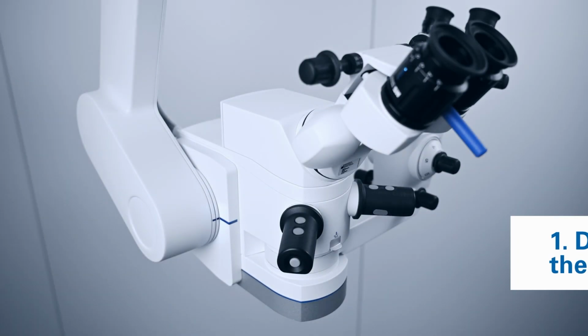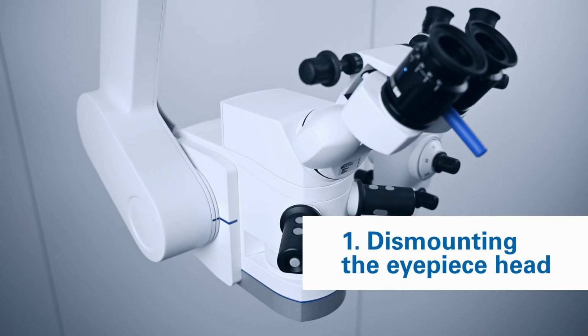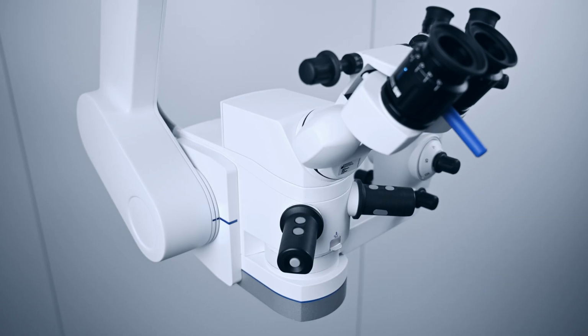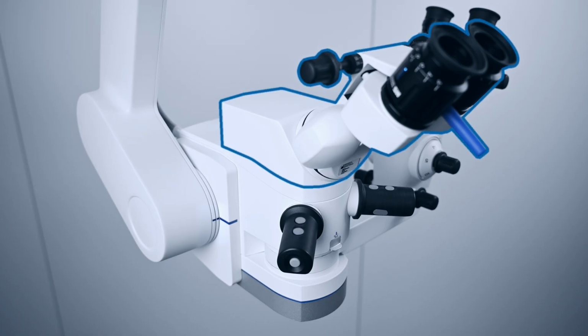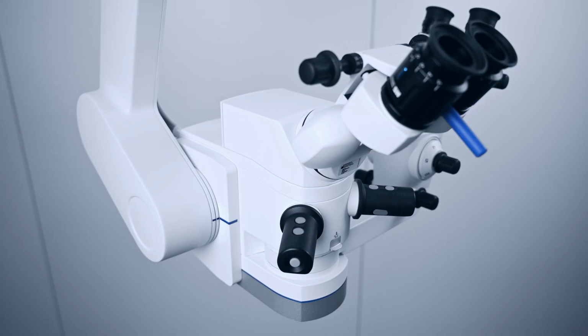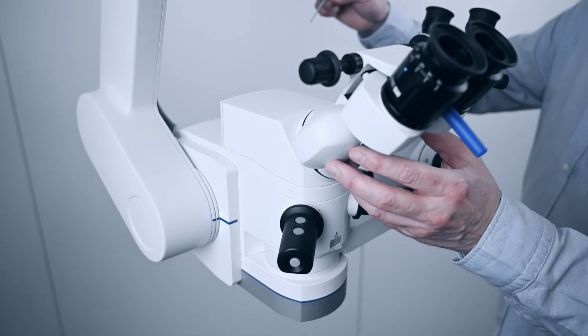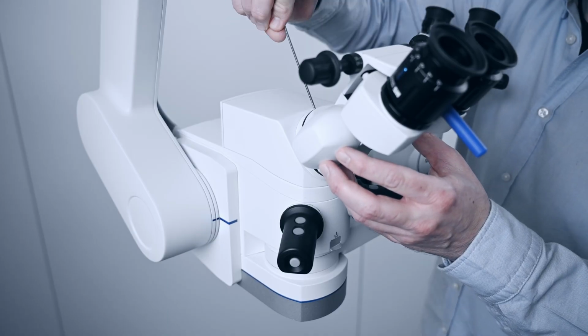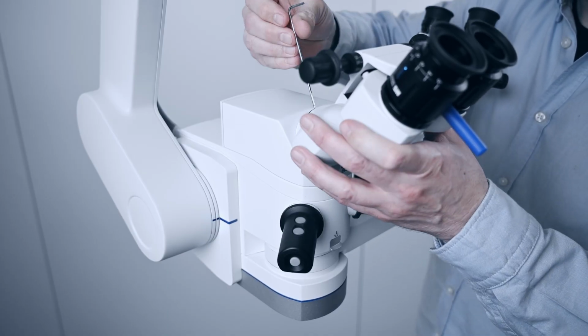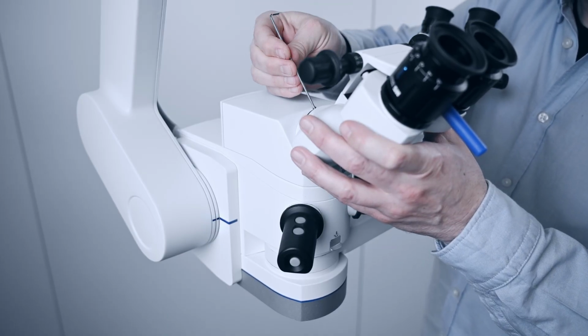Let's go into step 1, dismounting the eyepiece head. To use the METIS 900 microscope with METIS Heads-Up, you must first replace the varioscope and eyepiece head with the 3D stereo camera unit. Take the size 2 Allen key from the monitor trolley drawer. Using the Allen key, loosen the grub screw of the eyepiece head by rotating it in a counterclockwise direction.